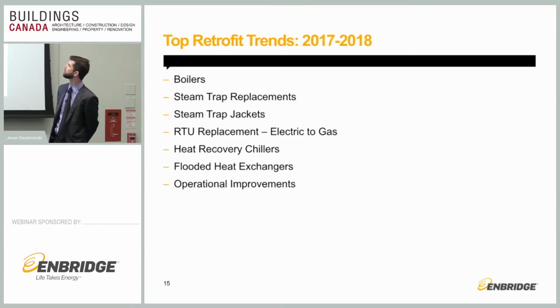Next, please, Zig. So the top trends we're seeing that I worked on this year, like I said, boilers, bread and butter, it has been, and it probably will continue to be until gas is gone. We have seen a lot of steam trap replacements. We do year-over-year replacements. So if any of your systems aren't operating with steam that is not leaking, give me a shout, let me know. There's a good opportunity for savings there, and Enbridge generally supplies a lot of the incentive. Right now we're doing up to 20 cents per cubic meter on a steam campaign, so we're going to get a lot of the steam trap replacement costs paid for.